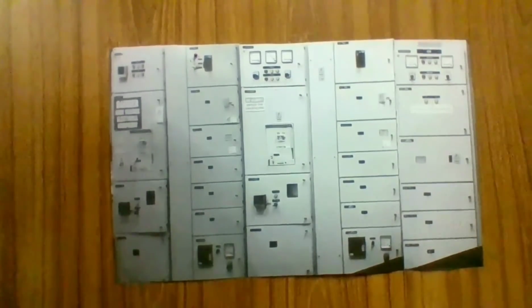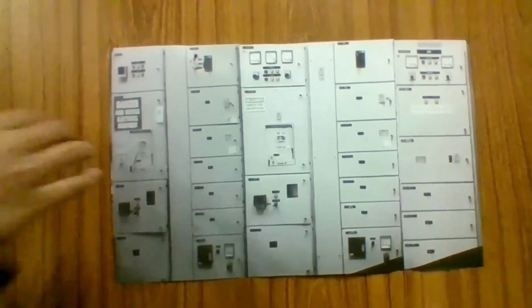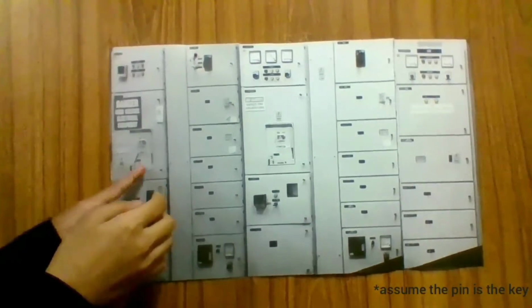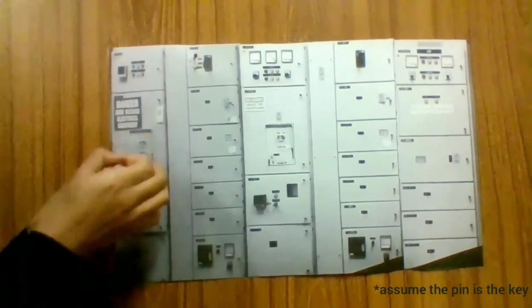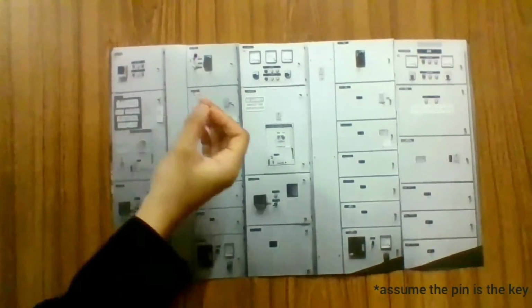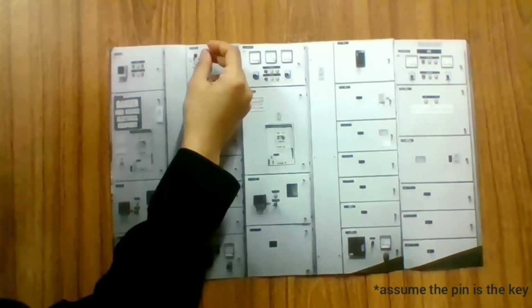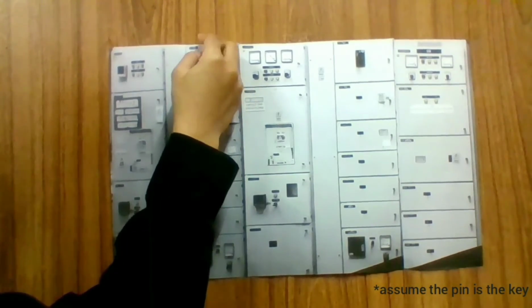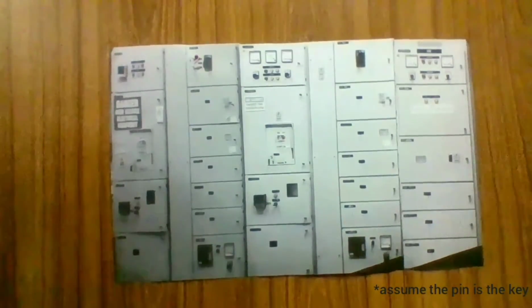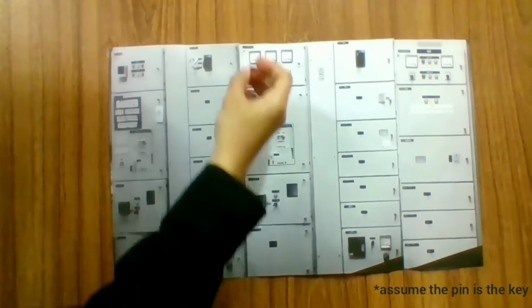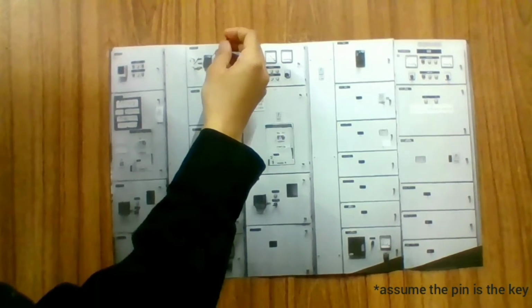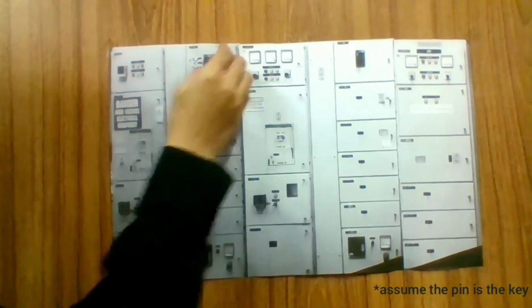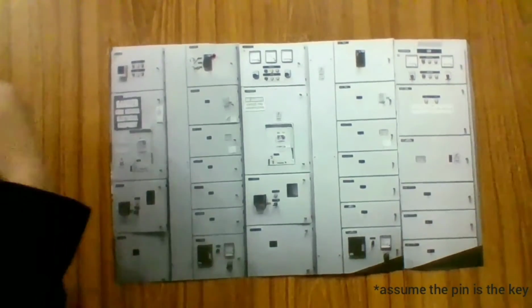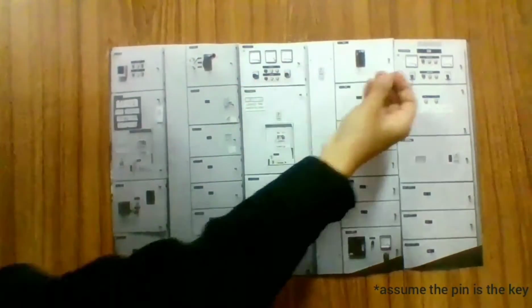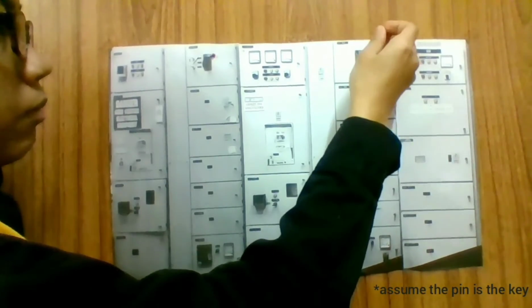For the busbar coupling process, first we need to take out the ACB key by holding the red button and rotating the key anti-clockwise at the same time. Place the key at MSB1 and rotate clockwise to get the C1 key and C2 key. The C1 key is used for the C1 isolator on MSB1 and the C2 key for the isolator on MSB2.